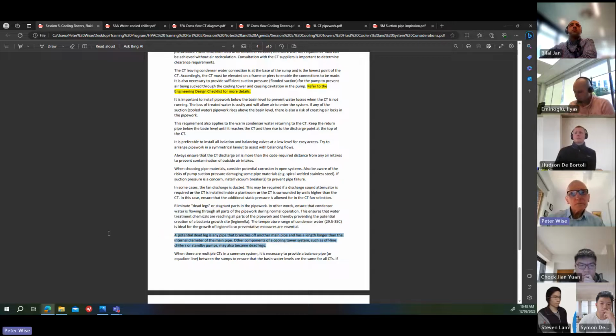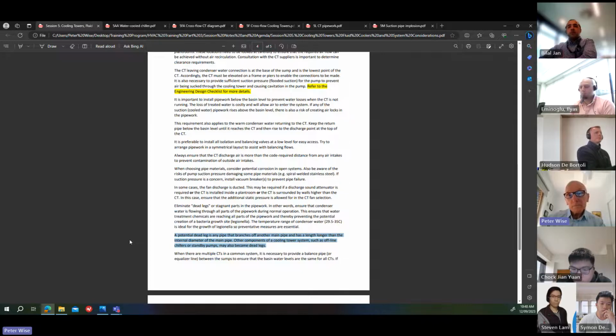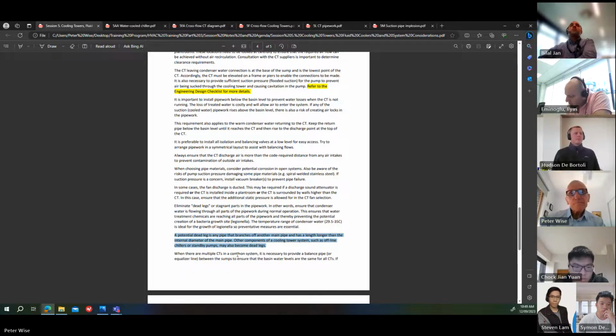Some people ask, how do you define a dead leg? So here's a definition that's probably useful to you. It's any bit of pipe that branches off another main pipe and has a length longer than the internal diameter of the main pipe. So if you've got a main pipe of 150 and a branch coming off which is 50, if it's longer than 150 long, it'll be considered a dead leg. So you need to design the piping system so that you've got water flowing through the whole piping system when it's running.